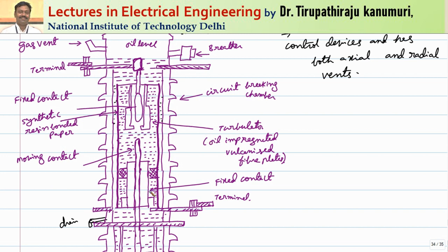There is also a fixed contact on the lower side connected to the supply terminals. Under normal operating conditions, the moving contact is in touch with both the upper and lower fixed contacts, conducting current. Whenever the contacts are separated to extinguish the arc, an arc is established between the contacts. The arc decomposes the oil, producing mainly hydrogen — nearly 1,000 times the volume of the decomposed oil — along with some other gases and carbon. This produces huge pressure inside the chamber.